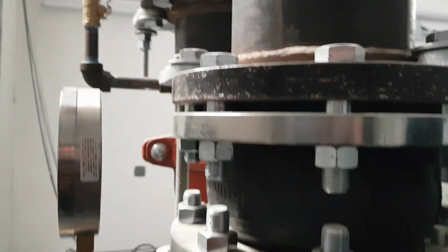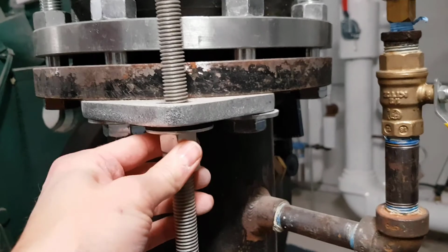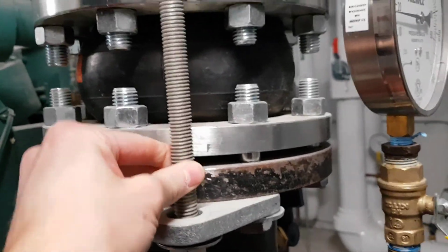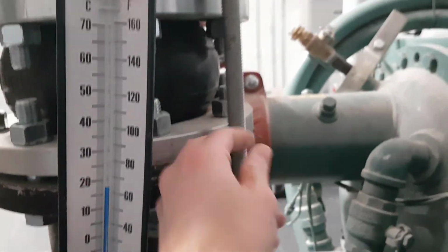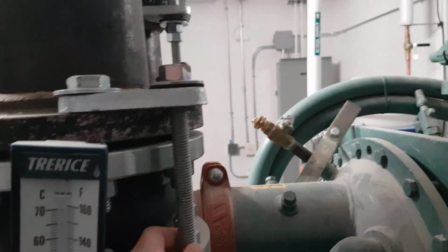Walking around to the second expansion joint, everything seems to be in good shape here as well. When I tried to move the control rod, however, I found it to be tight, meaning that either the expansion joint has extended to its maximum length, or more likely that the nuts were just set too tight. This isn't dangerous, but it could allow chiller vibrations to bypass the joint and find their way into the building and create noise.